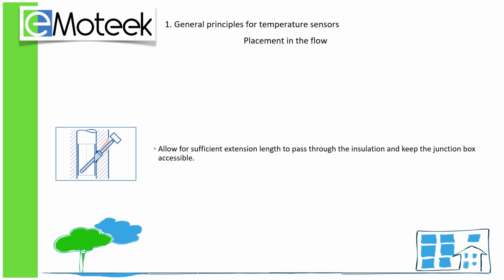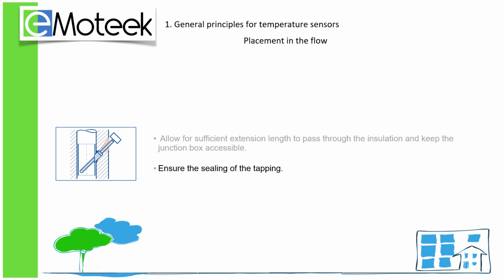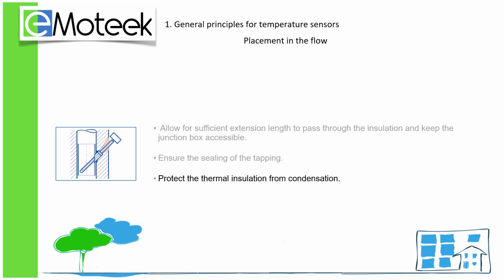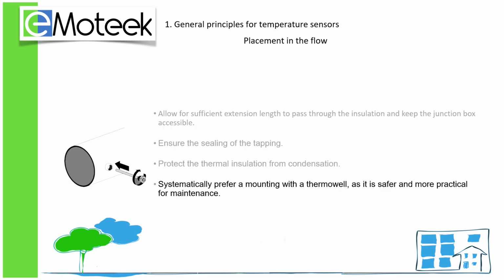For insertion into the flow, consider a sufficient extension length to pass through the insulation and keep the connection box accessible. Ensure the tightness of the tap. Protect the thermal insulation from condensation. Always prefer mounting with a thermal well. Oh really? Why? Because it's safer and more practical in case of maintenance.